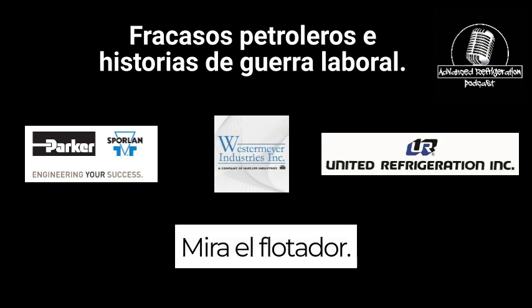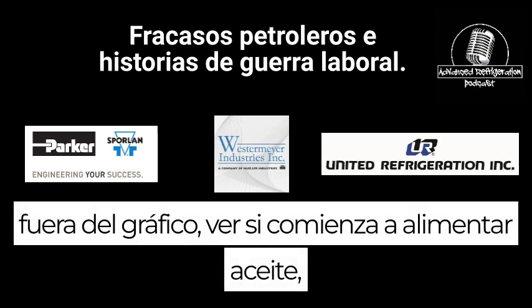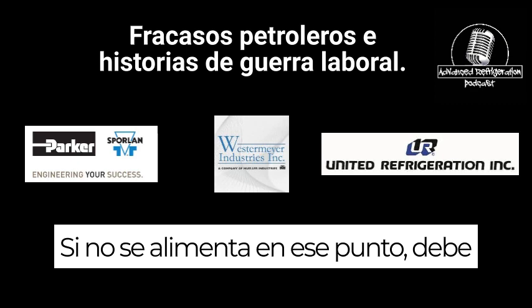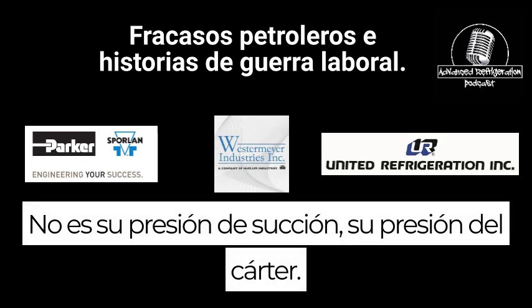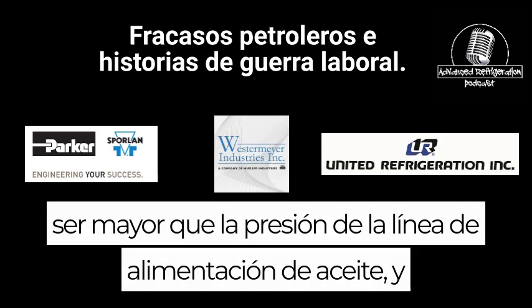Look at the float. I would inspect it and see how the float is. I'll reset the float off the chart and see if it starts feeding oil. See if it's set off the chart properly. If it doesn't feed at that point, you need to check a couple more things. Check your crankcase pressure, not your suction pressure, your crankcase pressure, because you could have an elevated crankcase pressure that is greater than the oil feed line pressure.